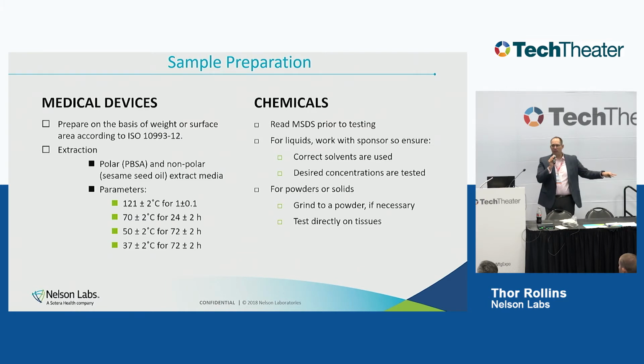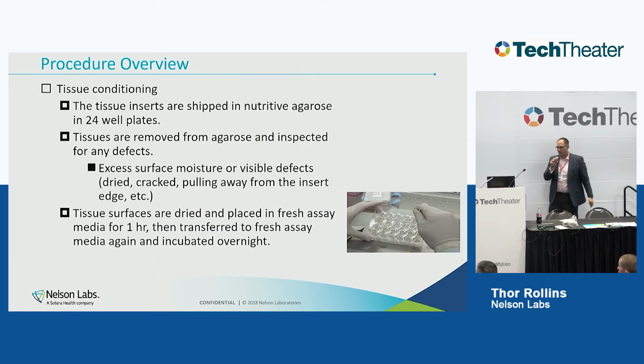It's been used already in the cosmetic industry and the pharmaceutical industry. We just wanted to make sure it would be sufficient for extracts from a medical device. So we did the extracts with the parameters that are in -12, and we were able to show that we're able to pull out these sensitizers from this polymer and then take a reaction in the skin cells. So that's what the validation was.